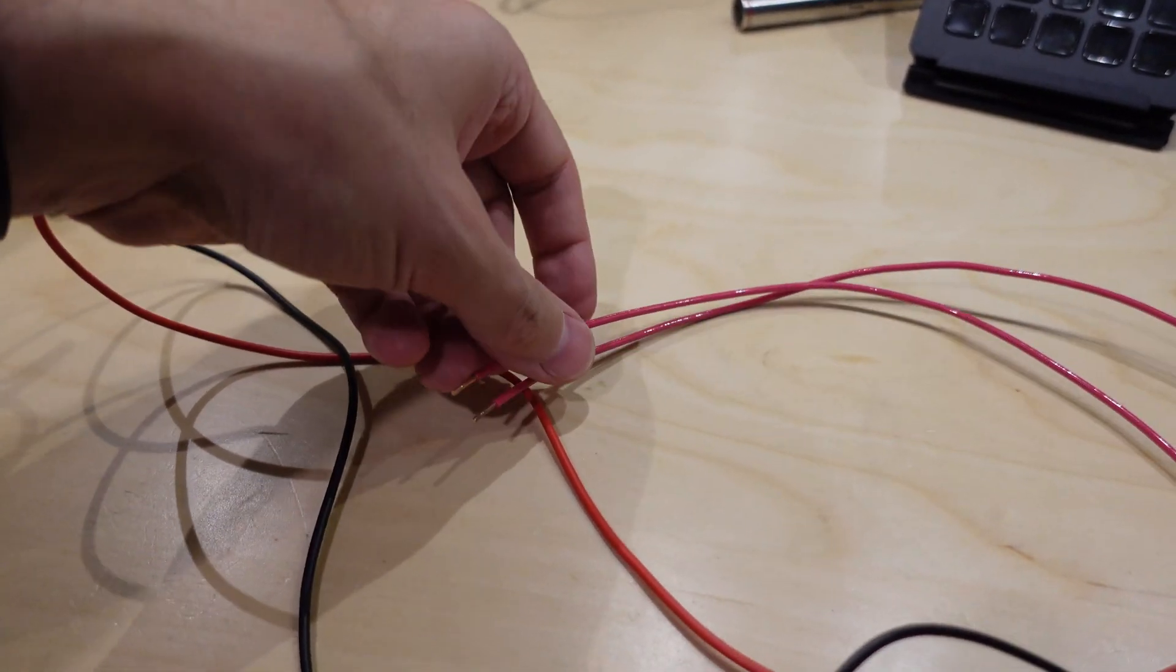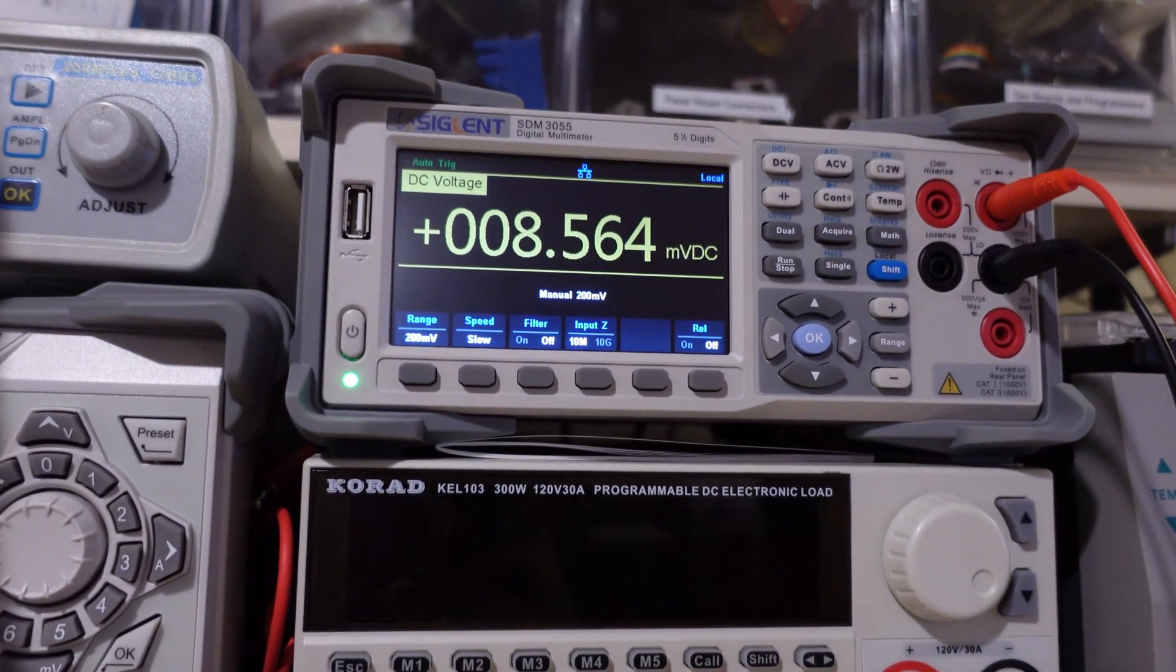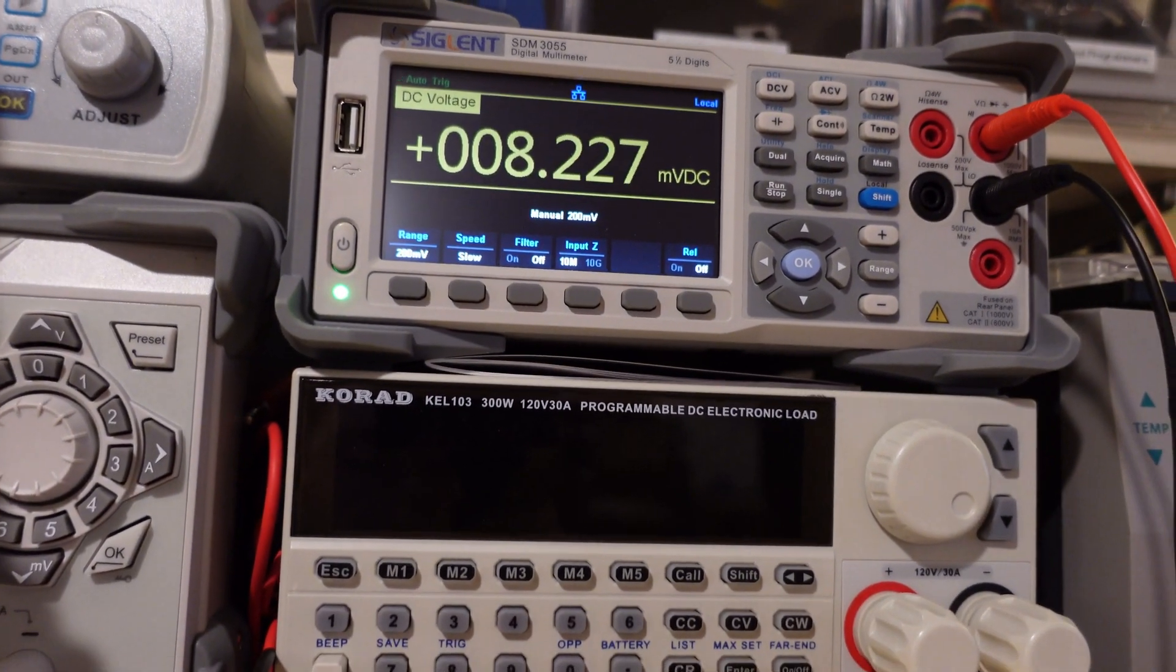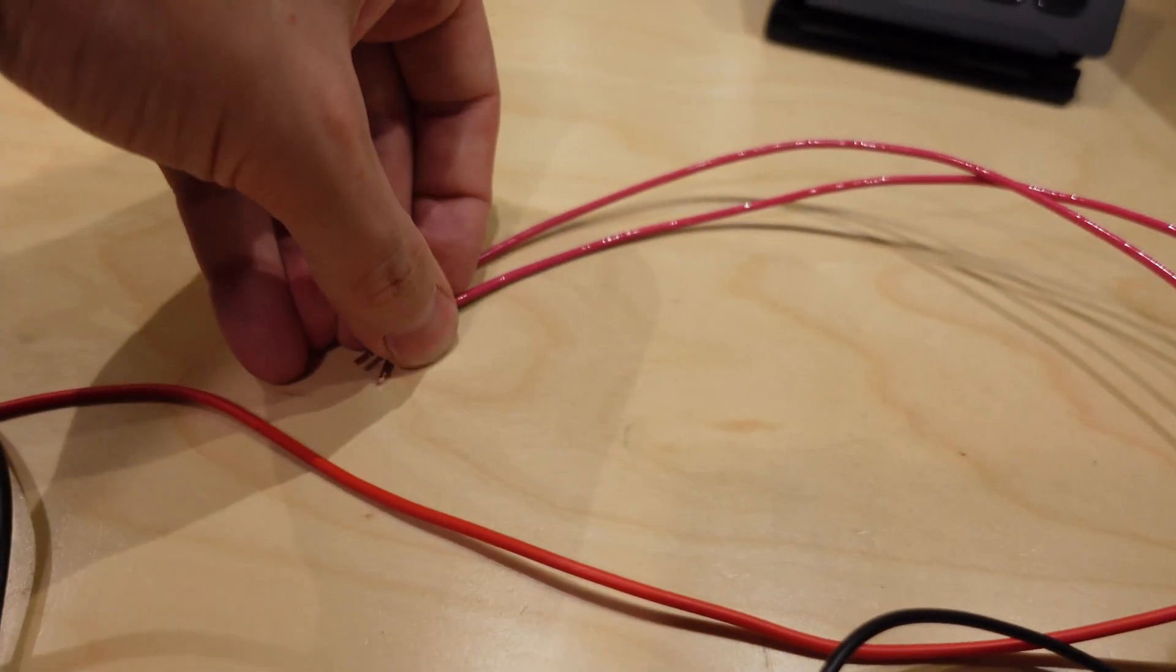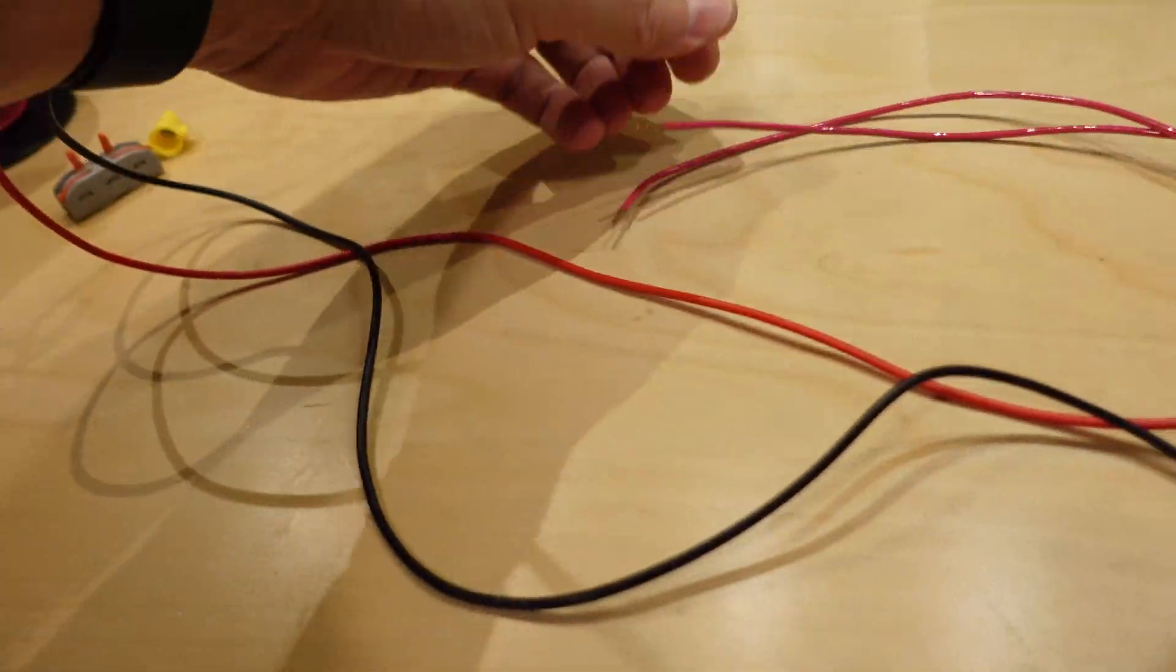What if I just touch these ends together? There we go. So I'm now just pushing on the ends of this, and you can see the resistance I'm getting here is around 8.3. So I actually, I can't do as well, even pressing really hard those together. In fact, it's a struggle even to get that 8. Yeah, so I'm just physically pressing as hard as I can. So that WAGO does a pretty good job of connecting those wires.